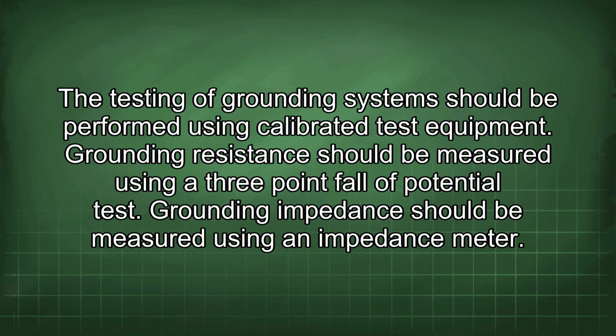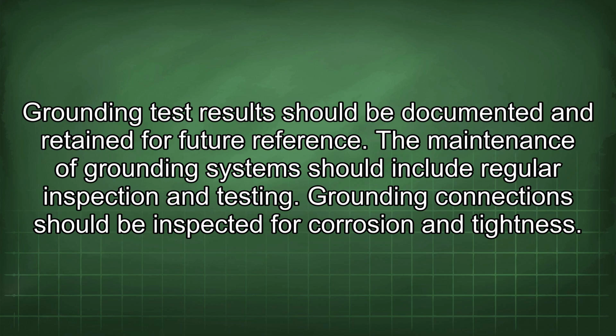The testing of grounding systems should be performed using calibrated test equipment. Grounding resistance should be measured using a 3-point fall of potential test. Grounding impedance should be measured using an impedance meter. Grounding test results should be documented and retained for future reference.